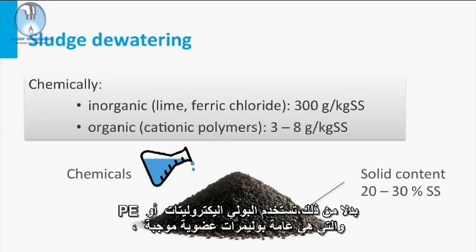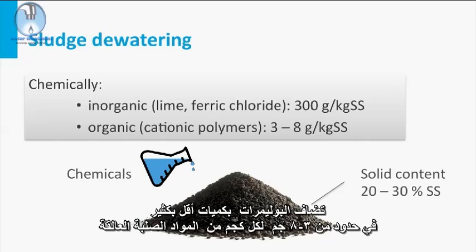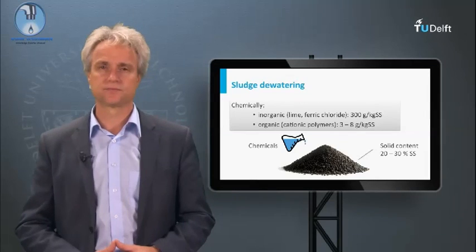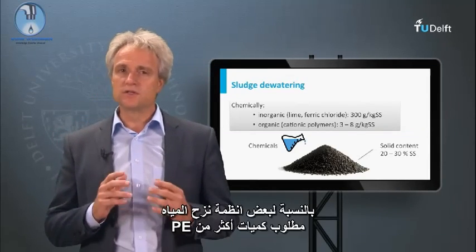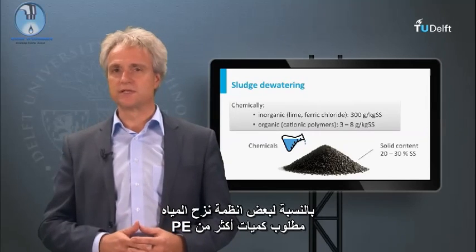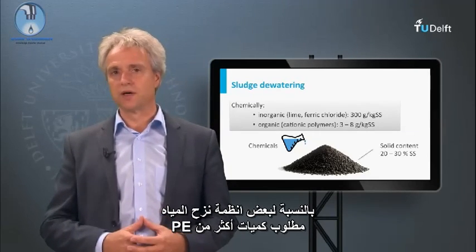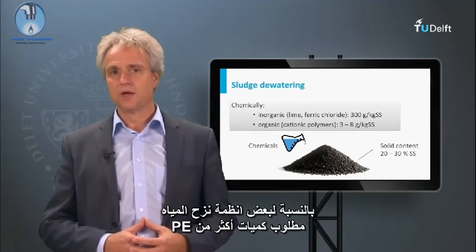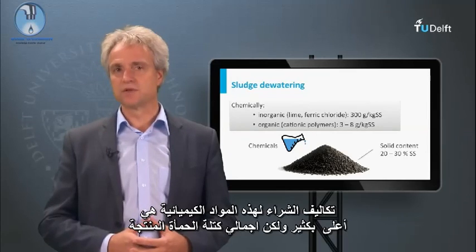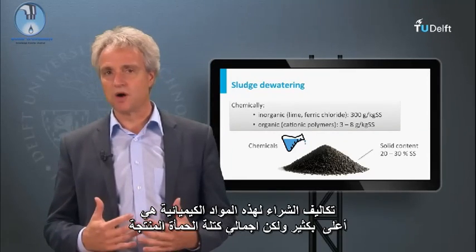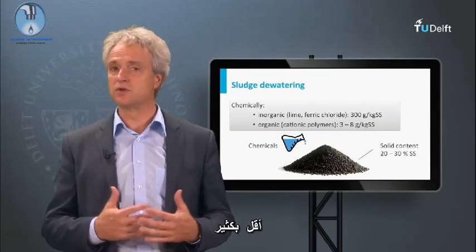Alternatively, polyelectrolytes (PE) are used, which are generally organic cationic polymers added in much lower amounts in the range of 3 to 8 grams per kilogram of suspended solids. For some dewatering systems, some more PE is required. The purchase costs for these chemicals are much higher, but the total sludge mass produced is much less.